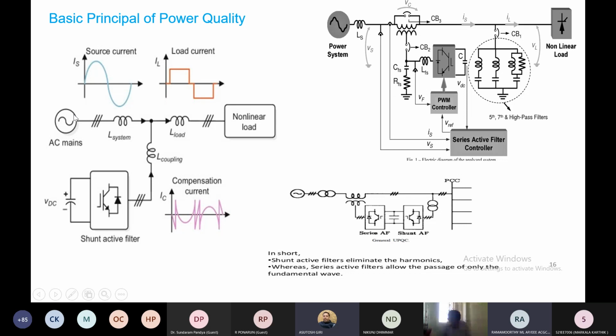Voltage will be sinusoidal, but load current will be in this nature. Definitely it is going to have some power factor, poor power factor, because the fundamental load angle will be different from the original sine component of the load current, and power factor problems will be there. More reactive power demand is kept on the supply, and some other heating related problems may occur.